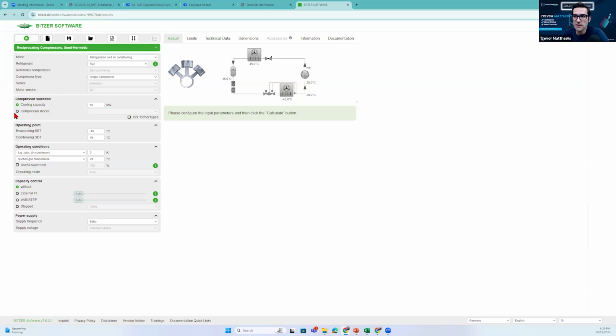You press this little button to pick a compressor model. So let's just randomly pick one. Let's do this one, a 4VE10. And let's hit the plus button up here and see what happens. Oh, look, it tells you that I can't use this compressor at a minus 40 application. So we have to do a minus 30 application. We hit plus again and see what happens. Oh, well, now our maximum condensing can only be 44 Celsius. Okay, so we go down to our SDT. We change that to 44 and we hit the plus button again because we're outside the envelope of that compressor.